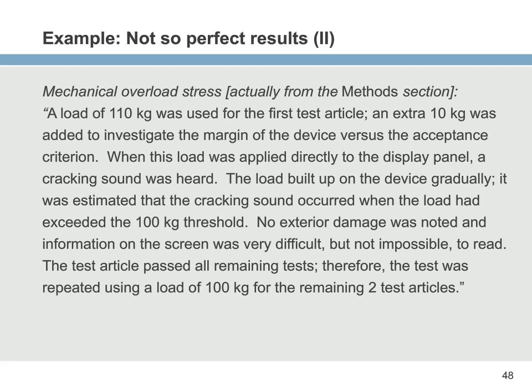When the test load was applied directly to the display panel, a cracking sound was heard. The load built up on the device gradually, and it was estimated that the cracking sound occurred when the load had exceeded the 100 kilogram threshold. So there's no proof, but no exterior damage was noted. The screen information was difficult but not impossible to read. The test passed all the other remaining tests, so all other angles of testing were fine.